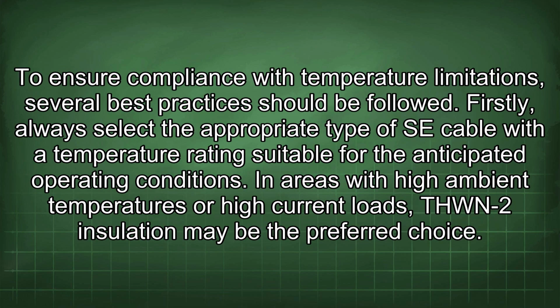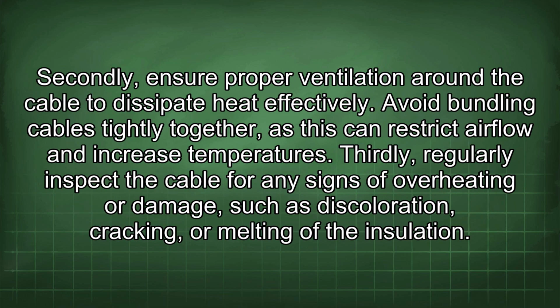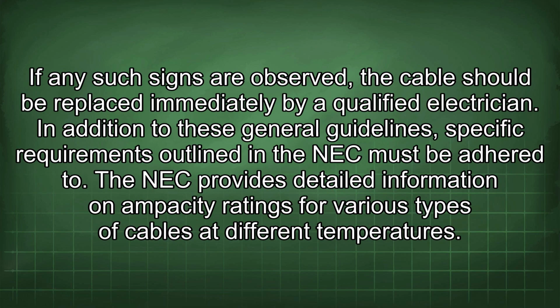To ensure compliance with temperature limitations, several best practices should be followed. Firstly, always select the appropriate type of SE cable with a temperature rating suitable for the anticipated operating conditions. In areas with high ambient temperatures or high current loads, THWN-2 insulation may be the preferred choice. Secondly, ensure proper ventilation around the cable to dissipate heat effectively. Avoid bundling cables tightly together, as this can restrict airflow and increase temperatures. Thirdly, regularly inspect the cable for any signs of overheating or damage, such as discoloration, cracking, or melting of the insulation. If any such signs are observed, the cable should be replaced immediately by a qualified electrician.